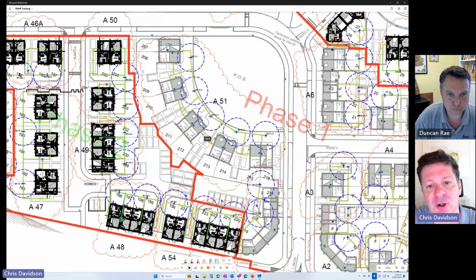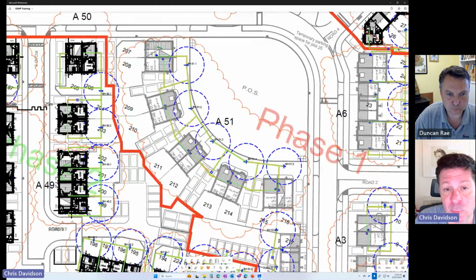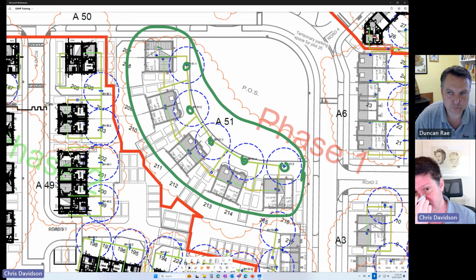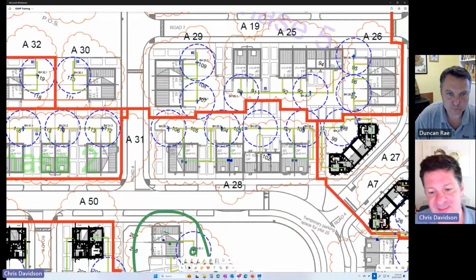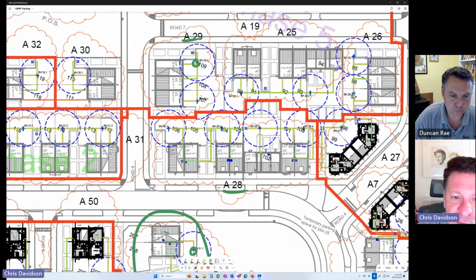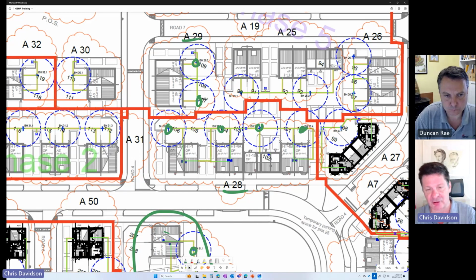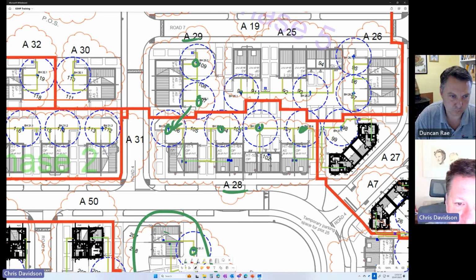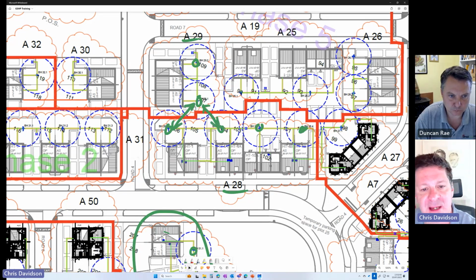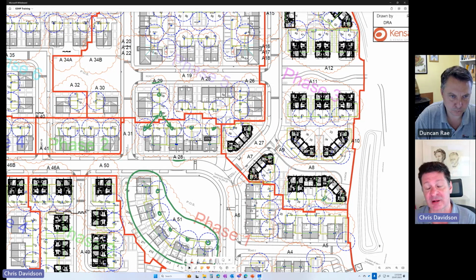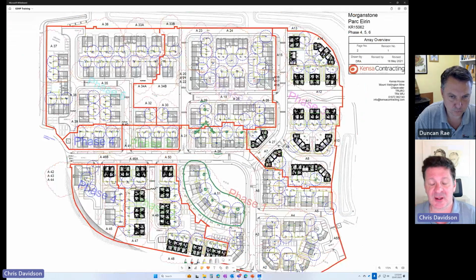So here we've got a little crescent, this is Parc Eirin in Wales, a Kensa Contracting project. It's been installed now for a couple of years. All the houses are now being occupied. And in this little crescent, we've got 5 boreholes supplying these 10 houses. So that's one district heat network there. Now, if we look up here at array 28 and 29, array 29's got a couple of boreholes feeding those dwellings, and array 28's got 4 boreholes. They are not in hydraulic contact with each other. They're separate systems. However, they are close enough together to be in thermal contact with each other. So when we're designing a project like this, we can't just look at each individual array and design that. We've actually got to look at the overall project because of the thermal interference between the boreholes.